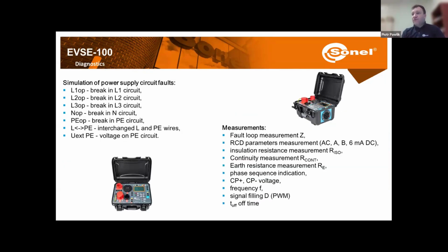Now further on, for checking different faults, we can check breaks on different circuits, we can check interchanged channels, and we can check voltage on the PE circuit. And as it comes to measurements themselves, we can measure fault loop impedance, we can check RCDs and RCMs, together with the requirement for DC leakage current over 6 milliamps. We can check insulation resistance, and we can check continuity, however here with the current of 200 milliamps.